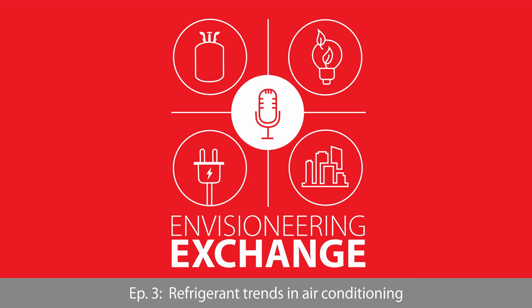Let's talk about chillers and where we are today and what the refrigerant options are going forward. Within the U.S., scroll chillers, which go up to about 250 or so tons, are using R410A almost exclusively today in North America. Larger chillers — screw compressors, centrifugal compressors, oil-free centrifugal compressors — are typically using 134A. As mentioned before, both of those refrigerants under the SNAP regulations are going to be disallowed.